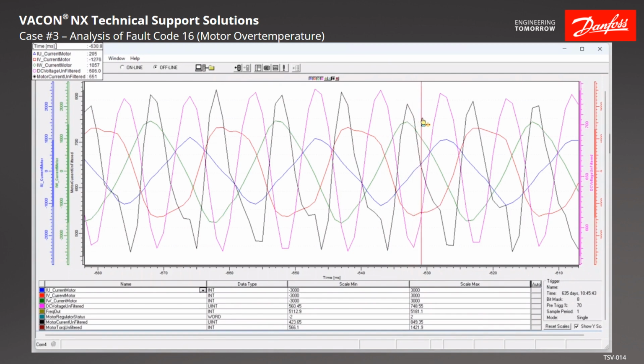Once we hit the bottom, we start to come back up. That means we're starting to draw off the line again. So this is a big area that we're drawing through there, so we're going to be heating those capacitors up quite a bit simply by the current draw that we're pulling through those capacitors. That, and we're stressing the rest of the drive also. Obviously your rectifiers, once you go to a single phase, your current goes up by 1.73 times. It's more current through there.